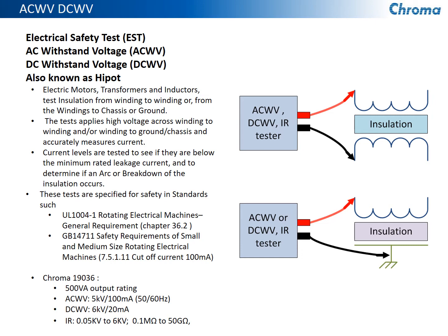Like I mentioned before, there are a lot of standards related to safety, and specifically for doing high pot testing of various devices. Two that come to mind are the ones used for motors: UL1004 is for electric motors, and also GB14711. That's a standard that requires a cutoff current up to 100 milliamps, and the 19036 AC withstand voltage tester handles that with no problem up to 100 milliamps. Insulation resistance is a similar test to the DC high-pot test, and it results in a measurement that is displayed in ohms rather than in amps and volts.